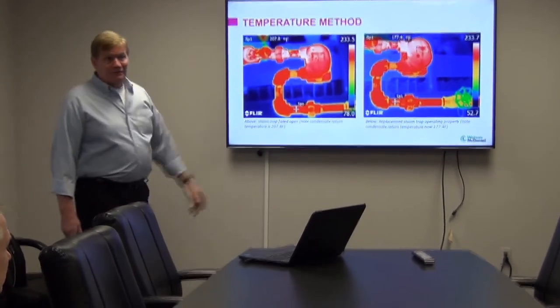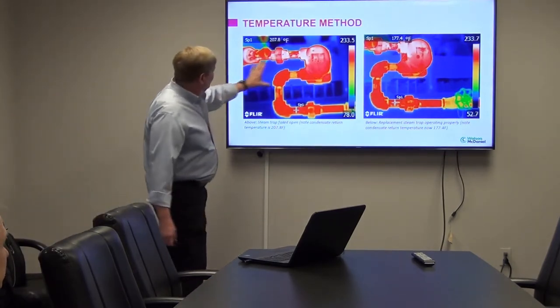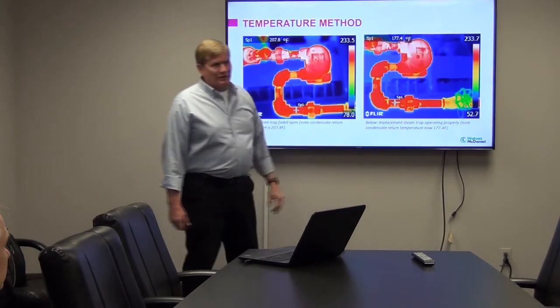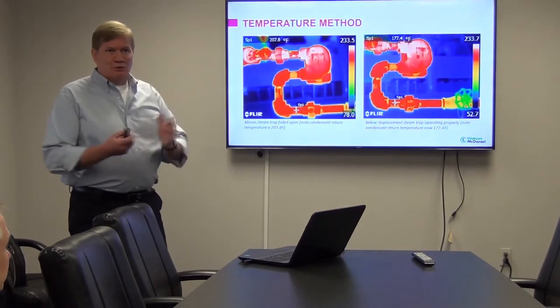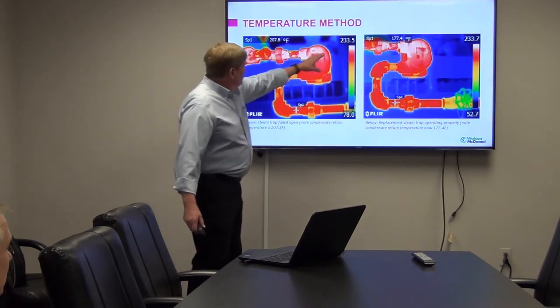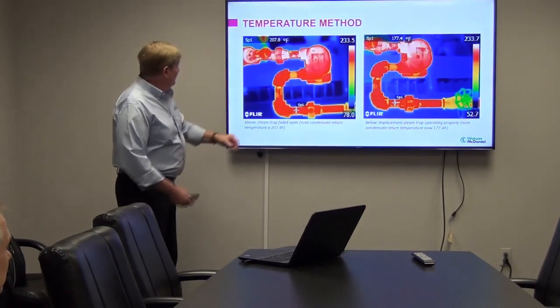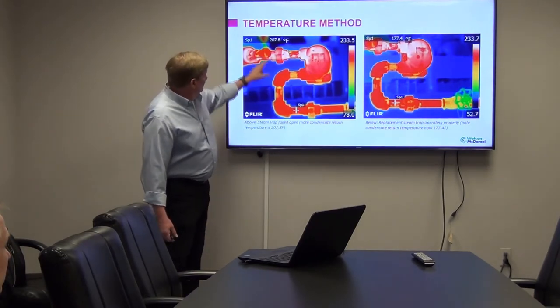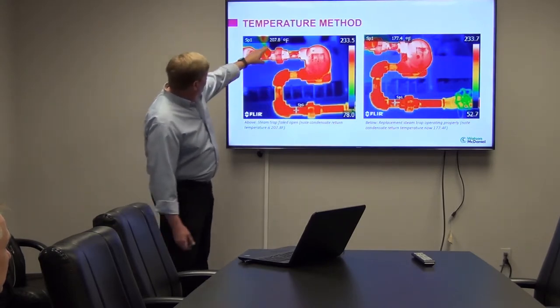Now this is with the Milwaukee infrared. This is nice, but you also always have to understand what pressure these systems are actually operating at. They put the temperature up here in the corner, that's telling me I'm around 10 psi steam pressure. For every pressure, there's a corresponding temperature, a temperature-pressure relationship. So if I'm around 10 psi, which is around 233 degrees, and I look here and it says steam trap failed open, you're looking at temperatures. Say, okay, I'm at 207 here.